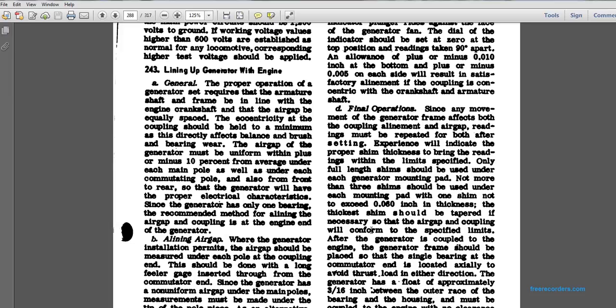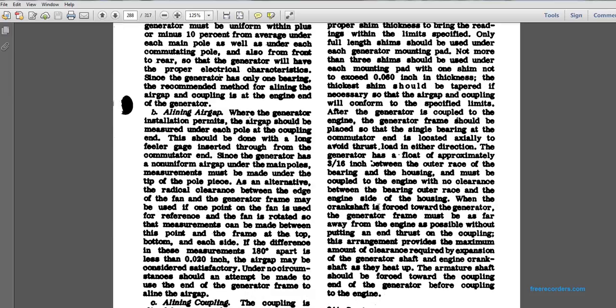Since the generator has only one bearing, the recommended method of aligning the air gap with the coupling is at the engine end of the generator. Aligning the air gap: when the generator installation permits, the air gap should be measured under each of the poles at the coupling, with a long feeler gauge inserted through the commutator end. Since the generator has a non-uniform air gap under the main poles, the measurement must be made under the tips of the pole pieces. As an alternative, radial clearance between the edge of the fan and the generator frame may be used. If one point of the fan is used for reference, the fan is rotated so the measurement can be made between the point of the frame at the top and the bottom of each side.